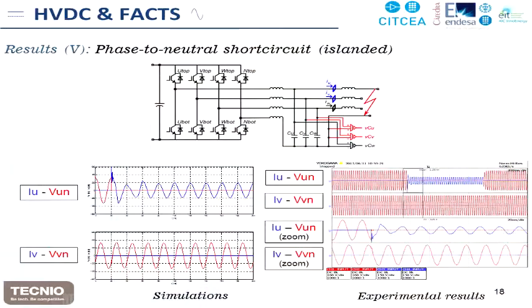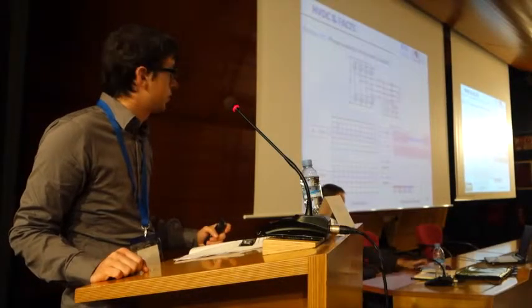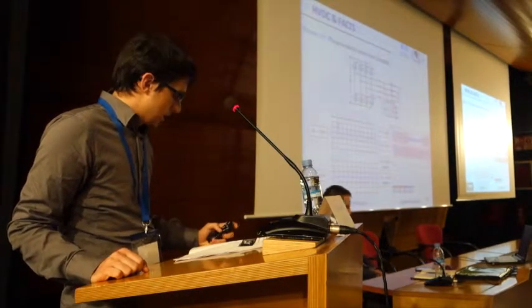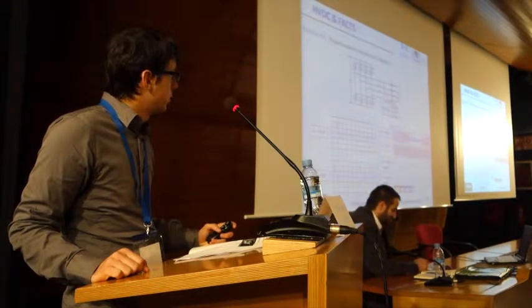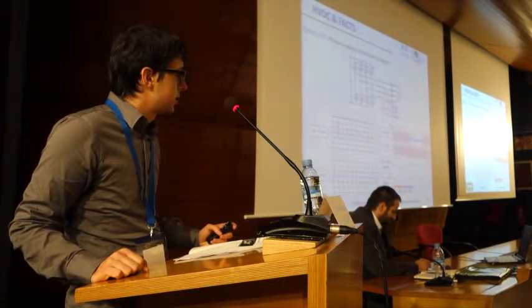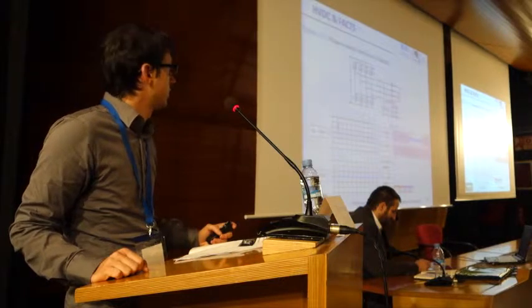Finally, two more results regarding the isolation mode. The first one is, well, here we have tested several short circuits. In this presentation, I only want to show one of them. In this case, it's a short circuit between the active phase U and the neutral wire. And the important point is that the system is able to manage the short circuit current up to the nominal rated current.